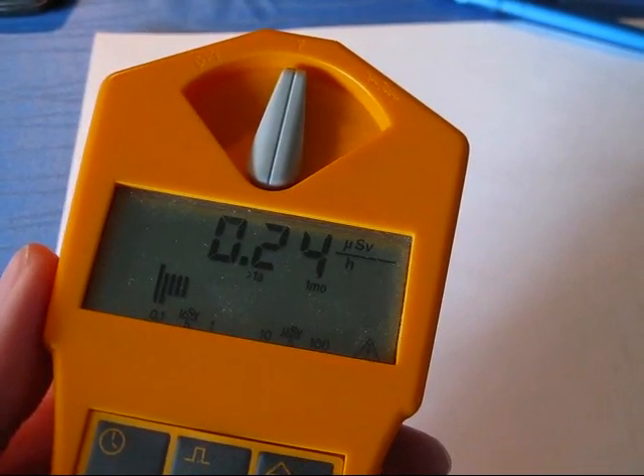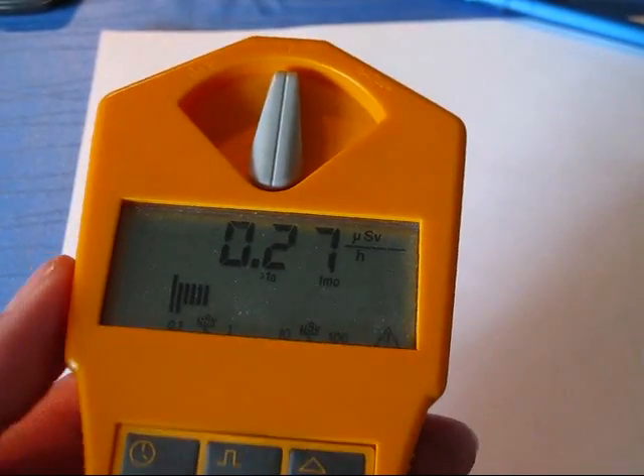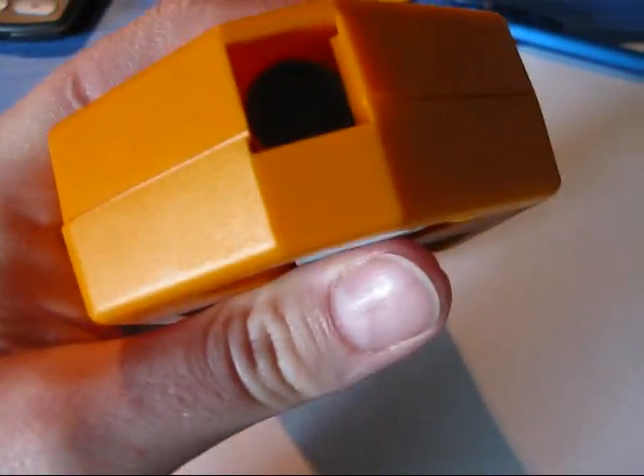Today we're going to determine the efficiency of a radiation detector. In this case, I'm using the Gamma Scout, which has a little Geiger-Müller tube inside with a thin mica window you can see just in front here. We're going to use these radioactive sources to determine the efficiency.